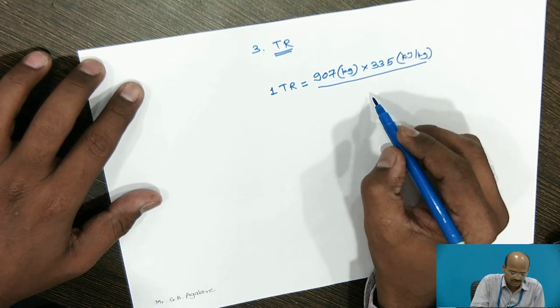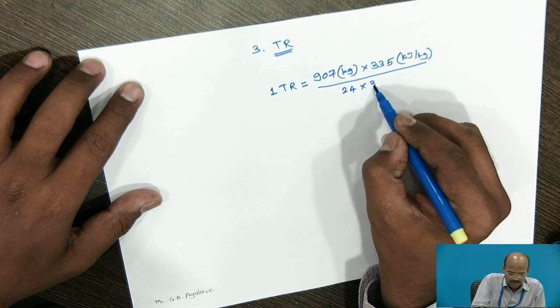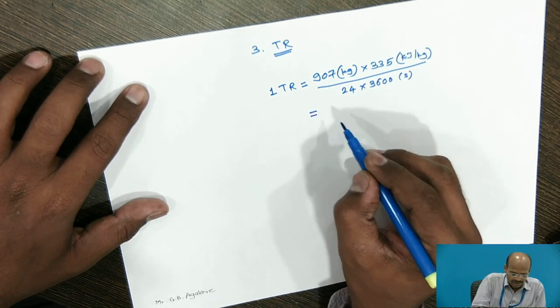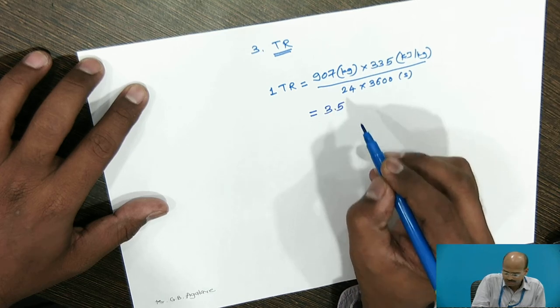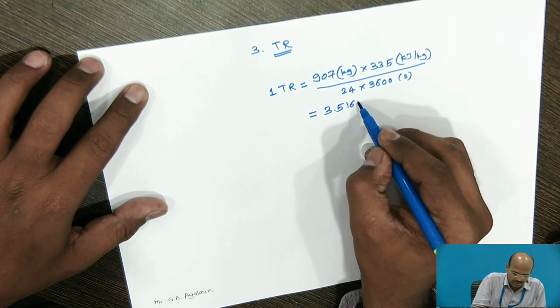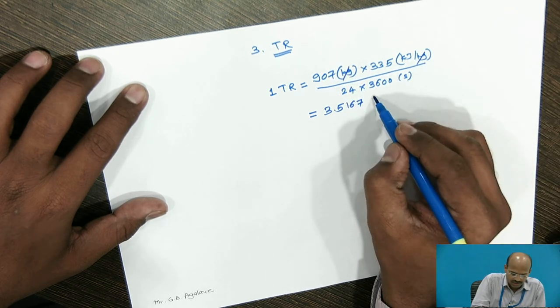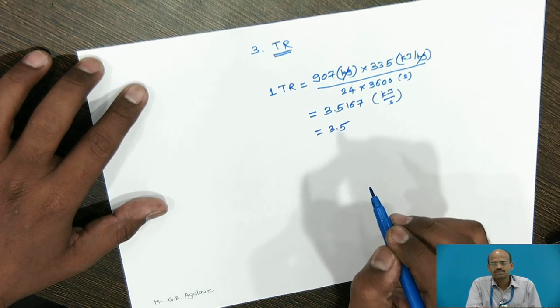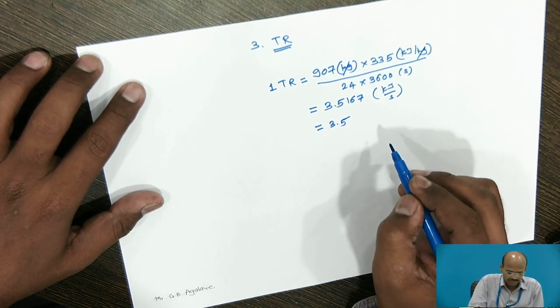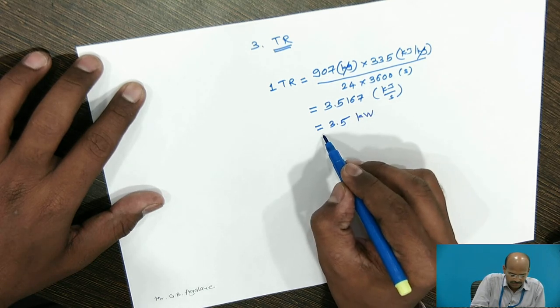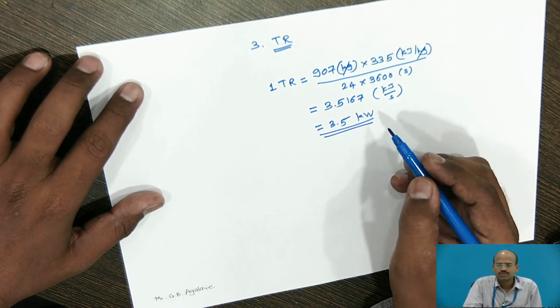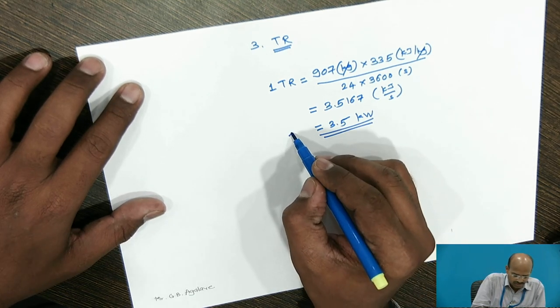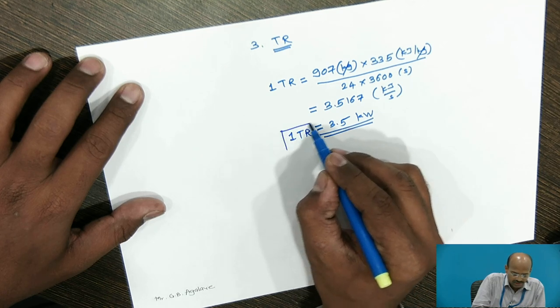1 ton of refrigeration will be equal to 1 US ton water. Here 1 US ton ice is nothing but 907 kg of water. This water is to be converted into ice means latent heat is to be removed from that water which is 335 kJ per kg. In 1 day or 24 hours to be converted into seconds. If we will do the calculation, then we will get the exact figure as 3.5167. Here kg kg will get cancelled, the unit will be kilo joule per second nothing but 3.5. For all calculations in refrigeration and air conditioning we will take 3.5 kW.